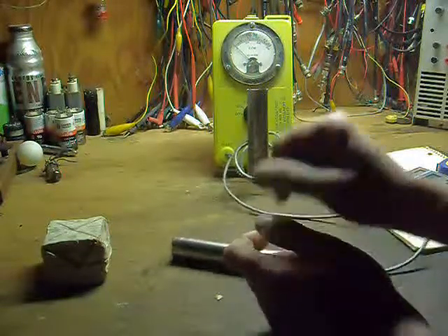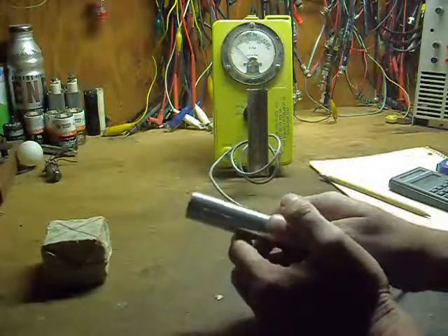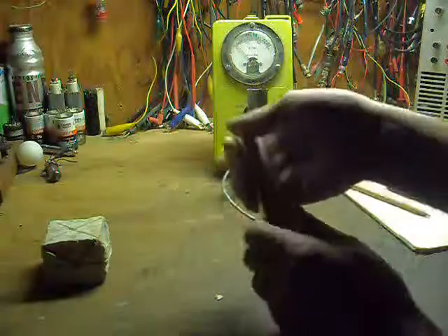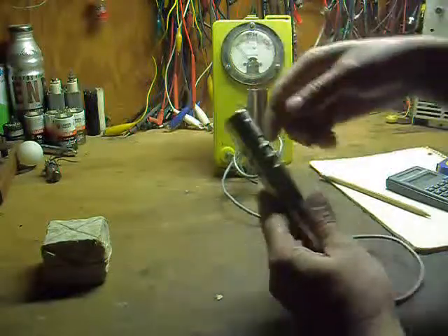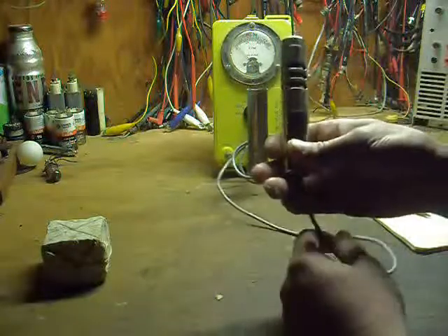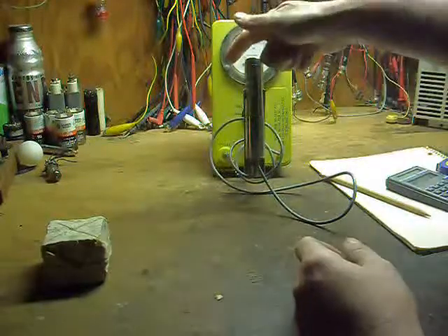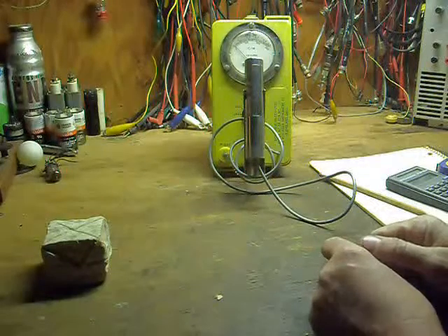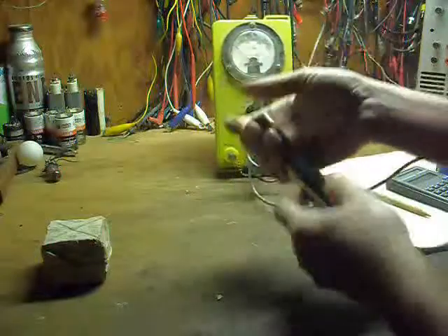Remember, after checking surface contamination, or when you are in an area where there may be radioactive elements that can come into contact with the probe, make sure to check to see if there is any evidence of radioactive contamination at the probe. That can be determined by putting the probe in a place you previously took a reading and seeing if the new reading is elevated over the previous one. That will give you an indication of possible contamination of the probe's surface.